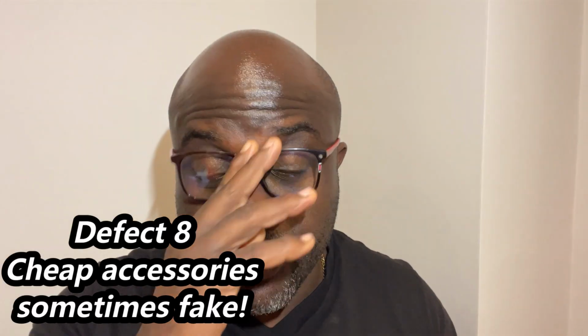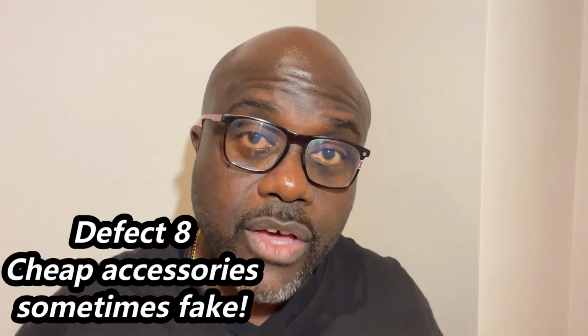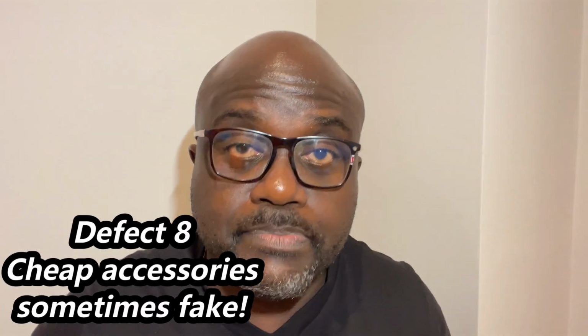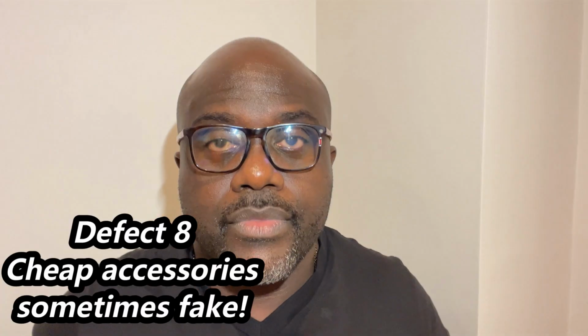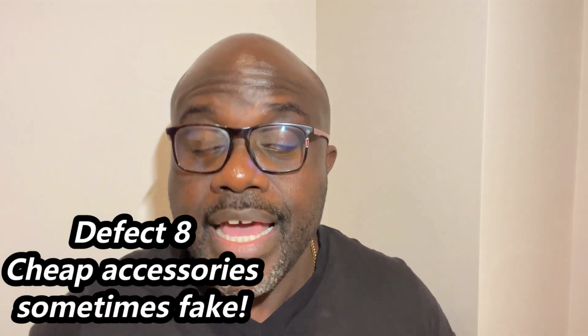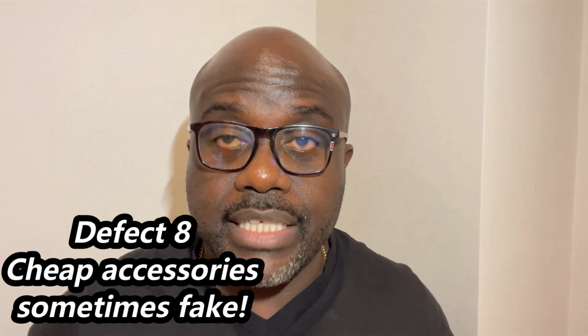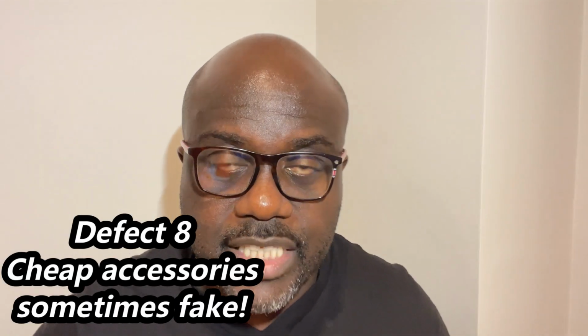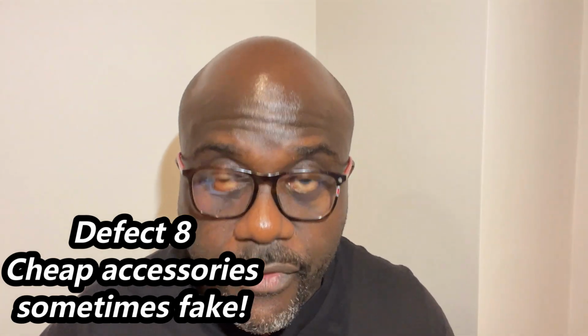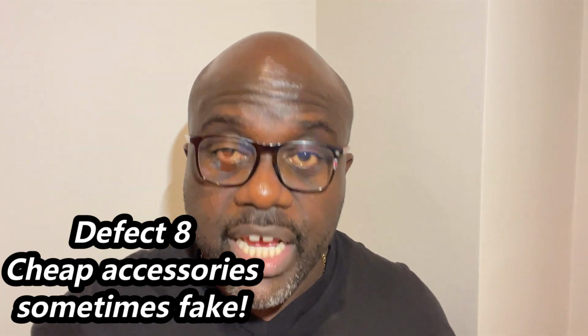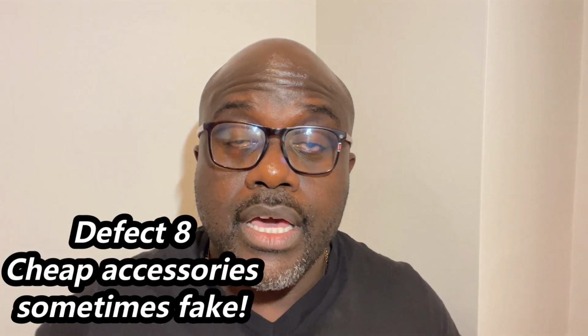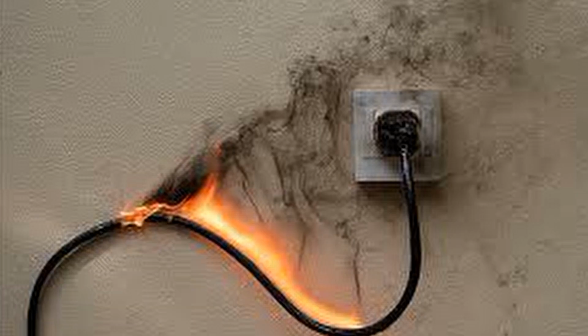Defect number 8. Sometimes you have cheap accessories, and unfortunately, I'll probably do a separate video on this. In the Ghana market, if you don't buy your equipment or accessories from the right place, you could be exposed to fake and counterfeit items. There's a way to spot them, and I'll cover that in a separate video. Counterfeit breakers, fake RCDs, low-grade sockets are prevalent in some parts of Ghana. Let's be honest. There are ways to avoid it, and there are many genuine places to buy from, so don't let that frighten you. Just have some awareness. If the device is cheap or fake, then it's not going to trip when it's supposed to trip. It may melt internally. It may fail under fault conditions. A breaker that doesn't trip is worse than no breaker at all.